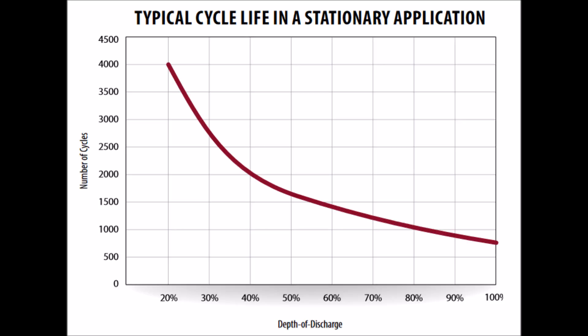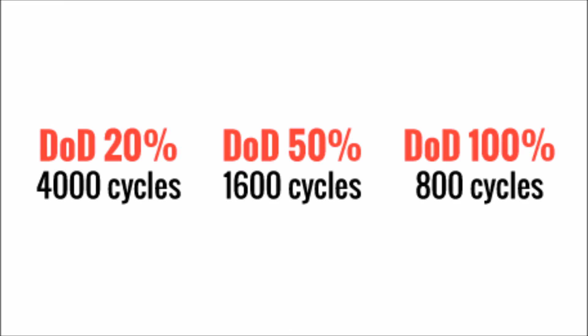Back to our Trojan T105RE battery for a second. This is a chart from the manufacturer showing the number of lifetime cycles on the left and the depth of discharge on the bottom. As you can see, the more that you discharge the battery, the lower the lifetime cycles gets. Past 50%, it gets pretty ugly. If we sized our battery bank so that we never discharged more than 20%, we would get 4,000 cycles out of those batteries. However, if we went to 50%, that would drop to 1,600 cycles, and going all the way down to 100% would only give us 800 cycles.